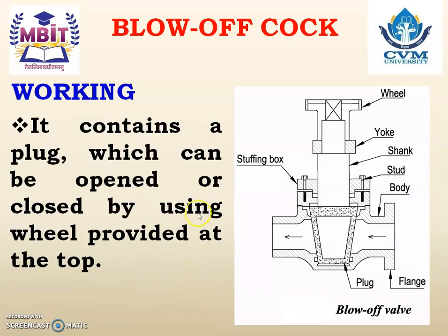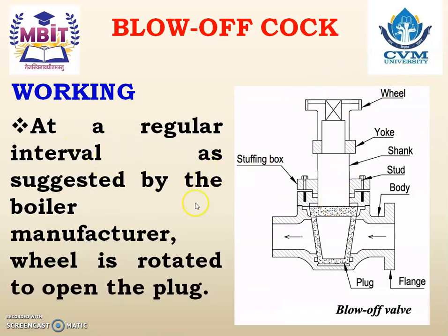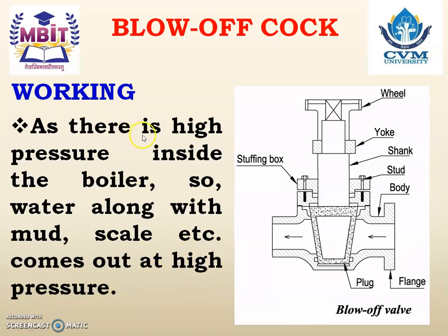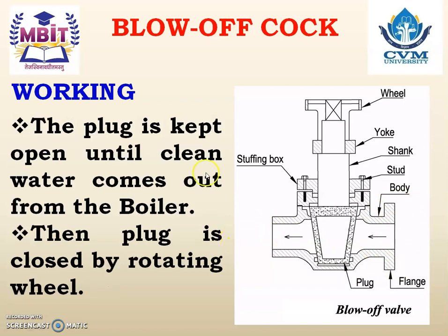It contains a plug which can be opened or closed by using the wheel provided at the top. At regular intervals as suggested by the boiler manufacturer, the wheel is rotated to open the plug. As there is high pressure inside the boiler, water along with mud, scale, and sediments comes out at high pressure. The plug is kept open until clean water comes out from the boiler, and then the plug is closed by rotating the wheel.